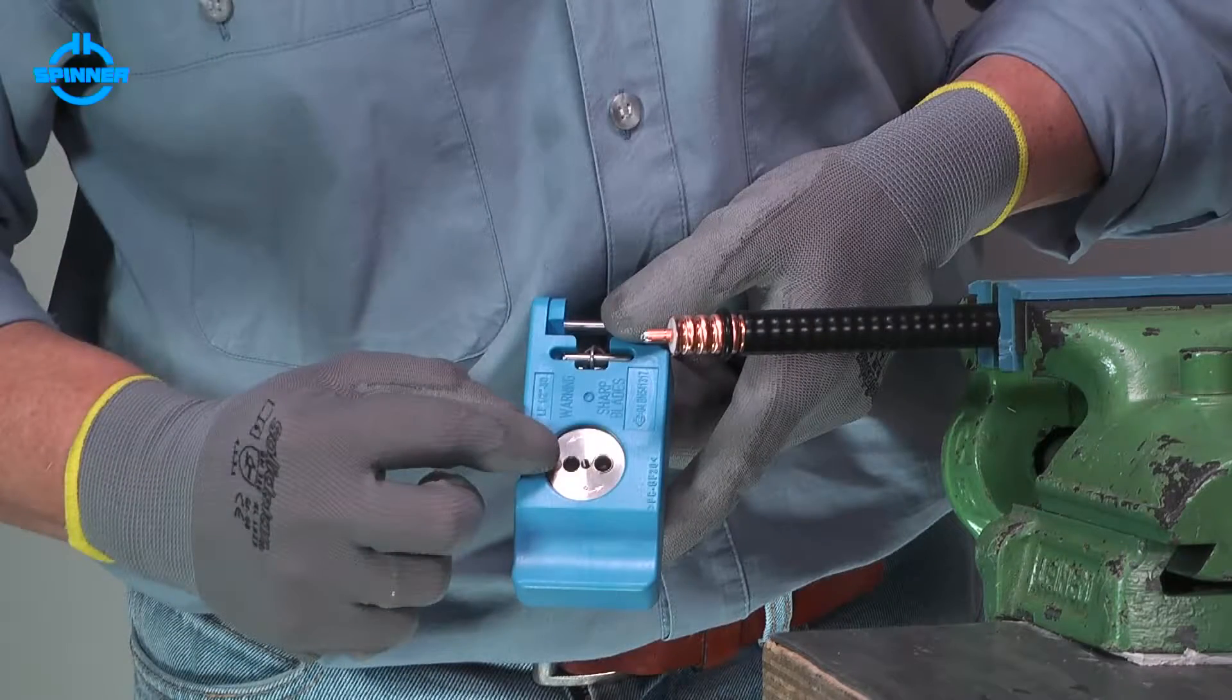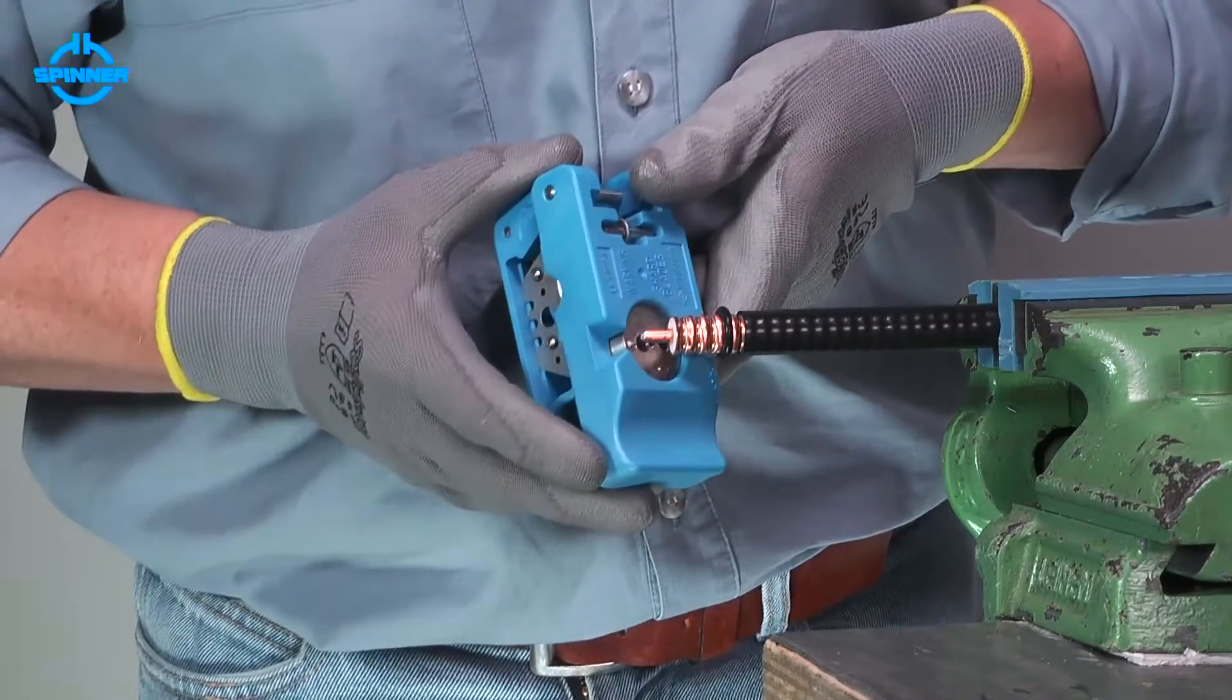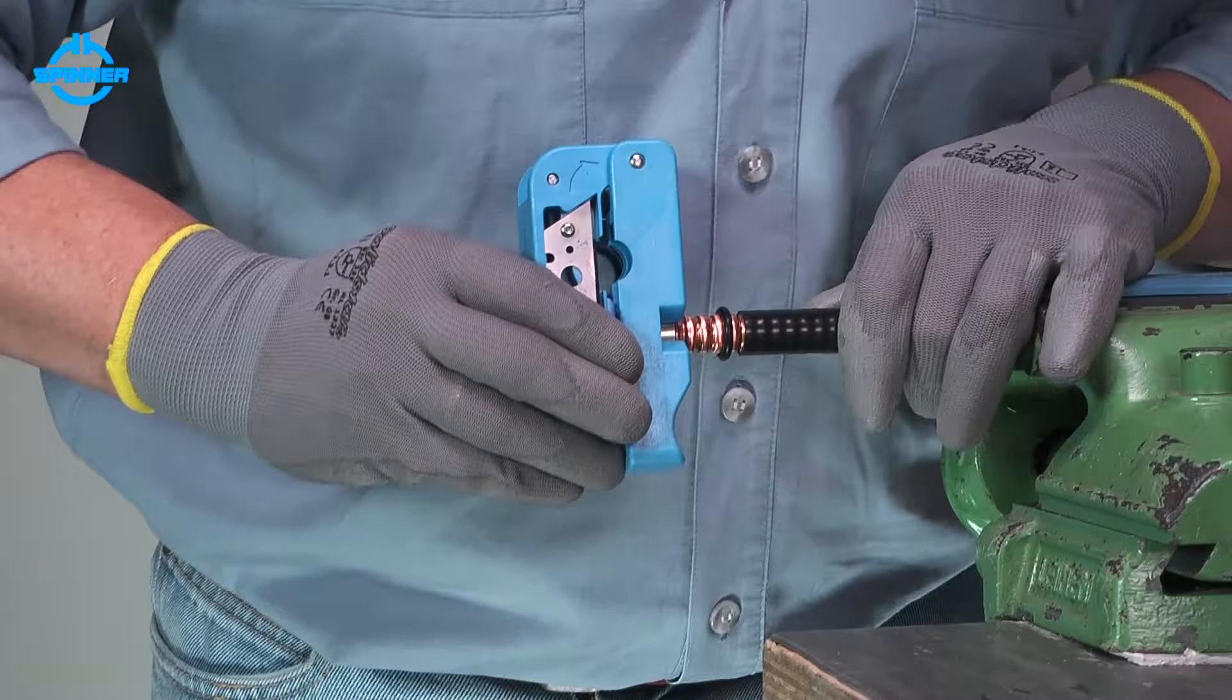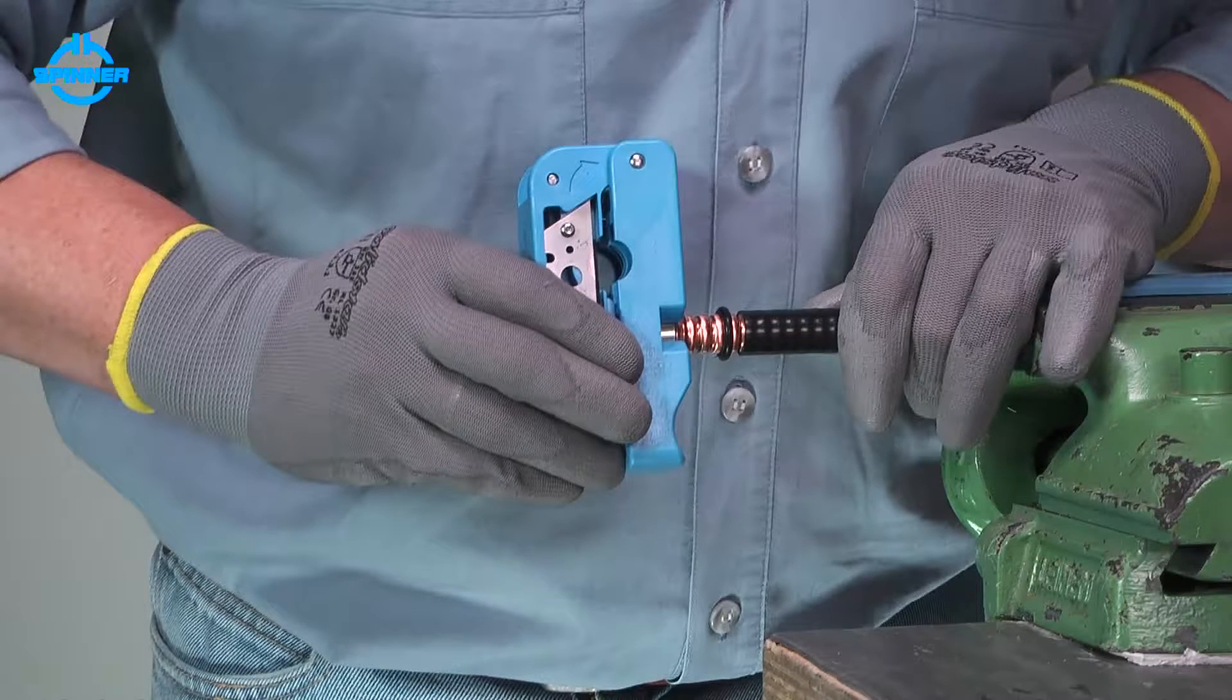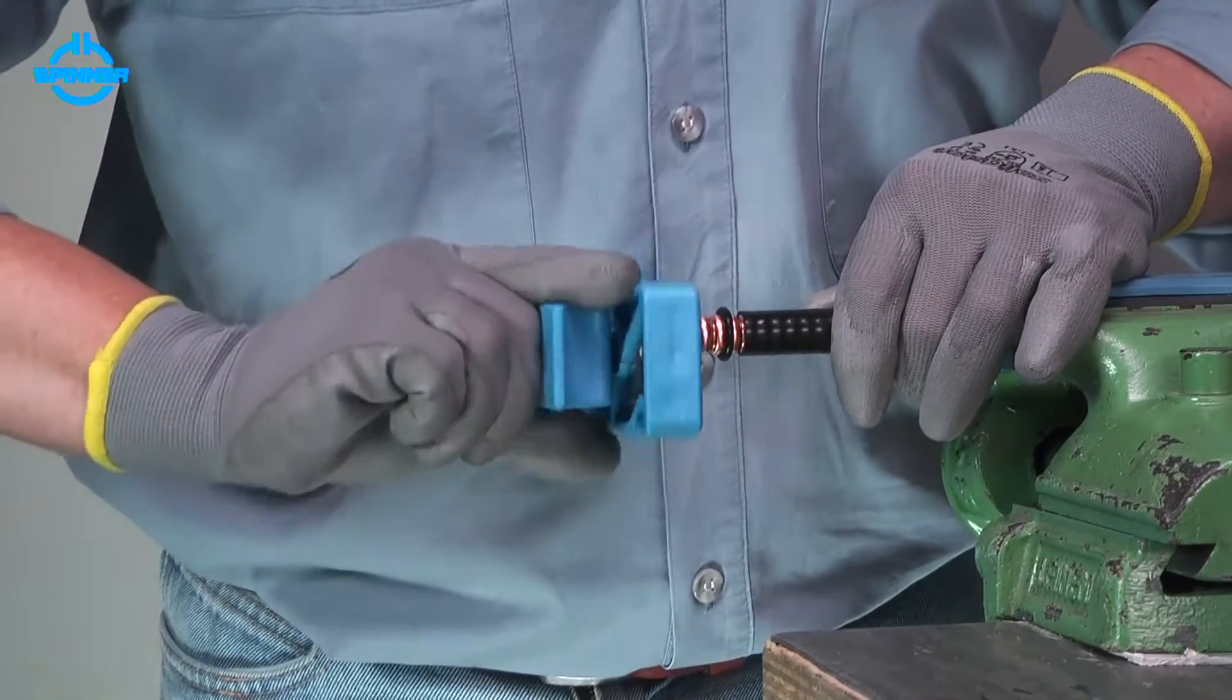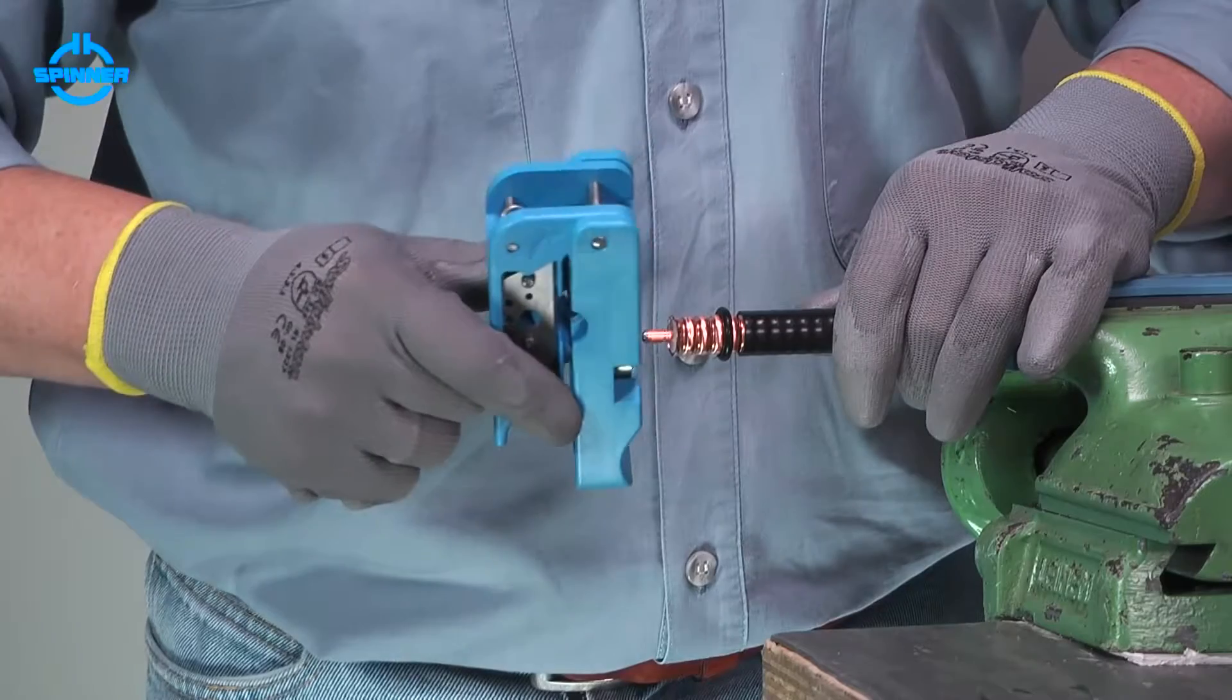Insert the flaring unit's guide hole onto the inner conductor. Ensure that the flaring unit's spike is positioned under the outer conductor. Turn the tool clockwise to flare the outer conductor.